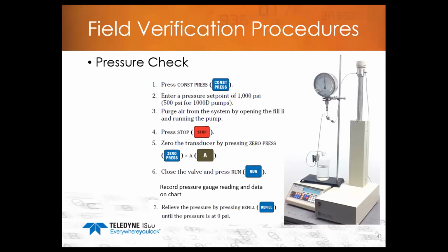And once again, you'll let the pump come up to that pressure, let it stabilize, and then if you need to, readjust R53 slightly to match the external pressure gauge reading to the pump. So basically it's a two-point calibration. We're adjusting at 1,000 psi, and then we're also adjusting at the maximum pressure of the pump.